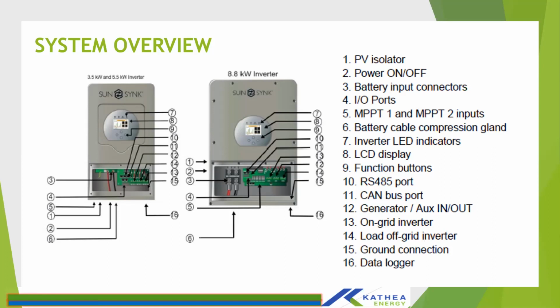So the inverter, as I've said earlier, is a pure hybrid inverter. So it will need to keep track of your grid and the load consumption, so that it will be able to backfeed to the loads and at the same time monitor for export. So the inverter comes with a built-in CT meter. So all you need is to wire the CT straight to the inverter. The points are provided on the inverter as well.